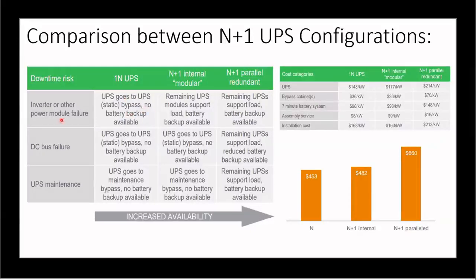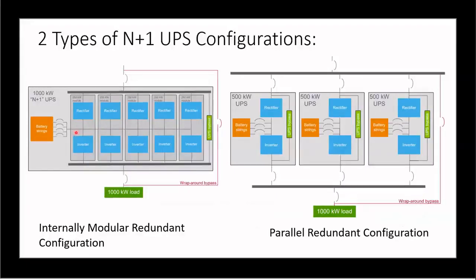So consider inverter or any other power module failure. Say if the inverter goes off, right? If there is no redundancy, then the UPS will go to the static bypass and no battery backup is available. But for the N+1 internal module, the remaining UPS modules will support the load and battery backup. So say if the inverter goes off. If there is no redundancy, then the load will be affected. But here, if this inverter goes off, then power will flow through the other UPSs, right? Here also it is the same.